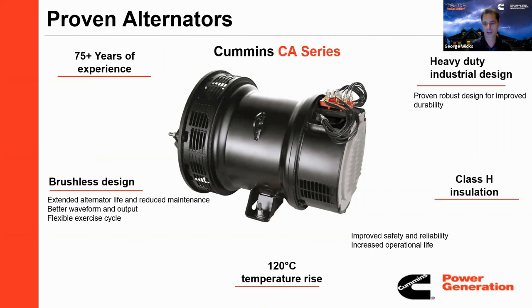There's the 120-degree temperature rise. In the fine print, some guys are rated at 130, some at 150. So that's how an alternator gets rated at full load capability at what maximum temperature.